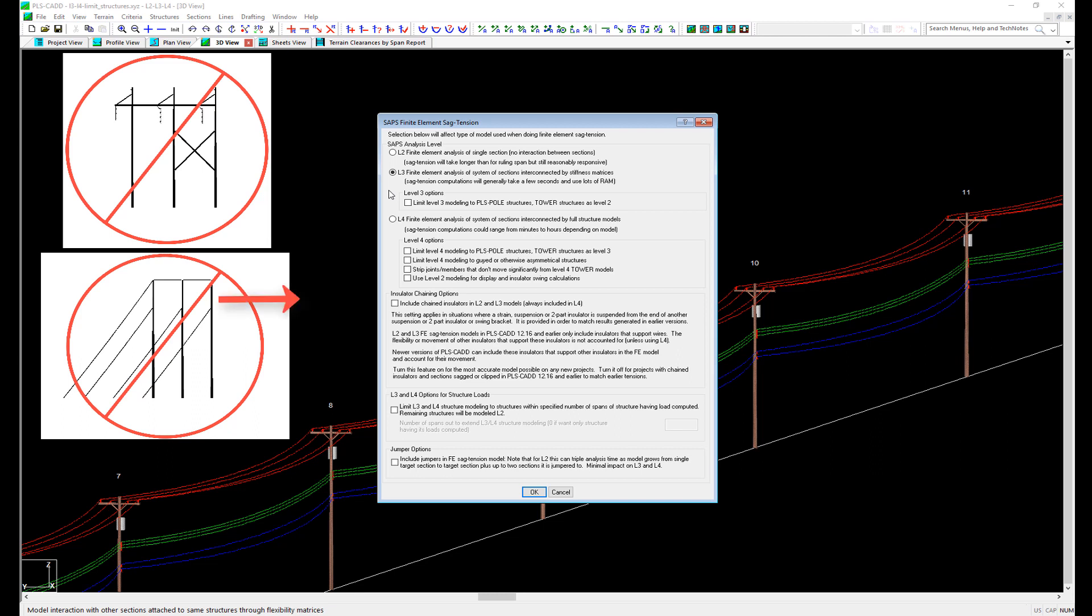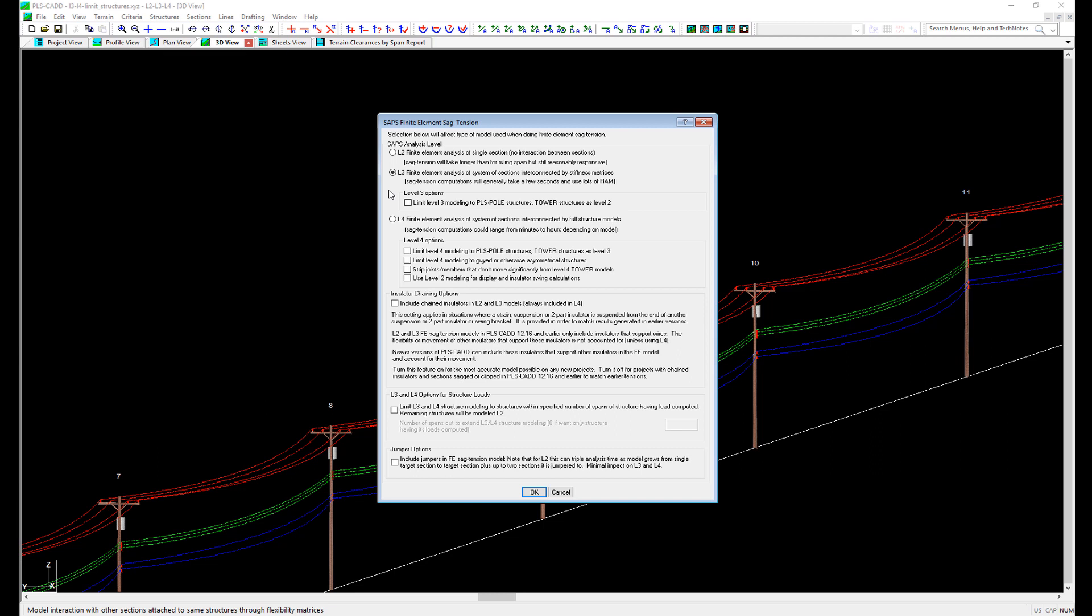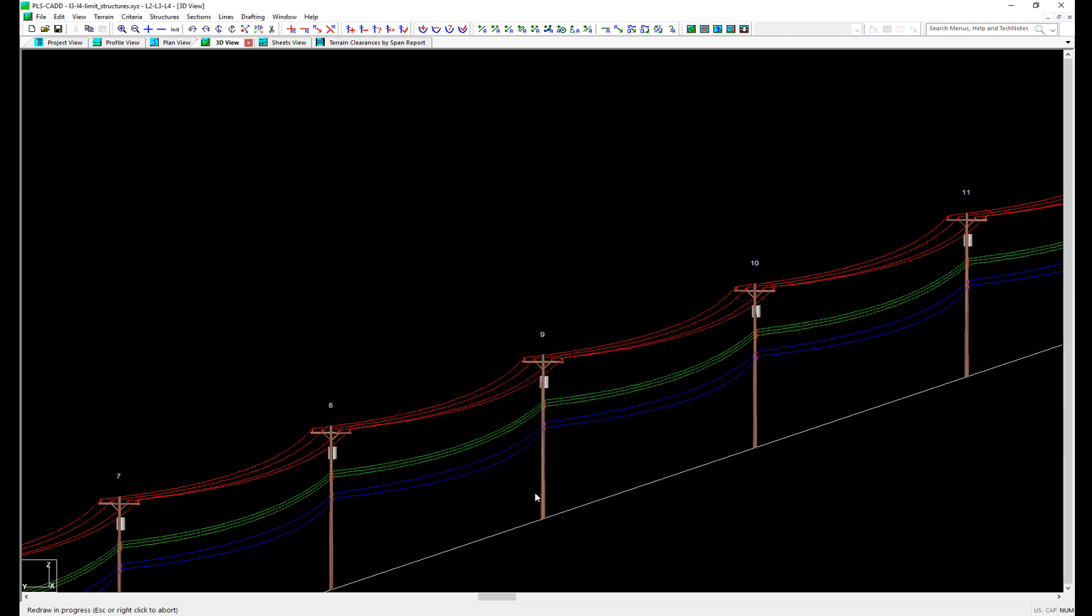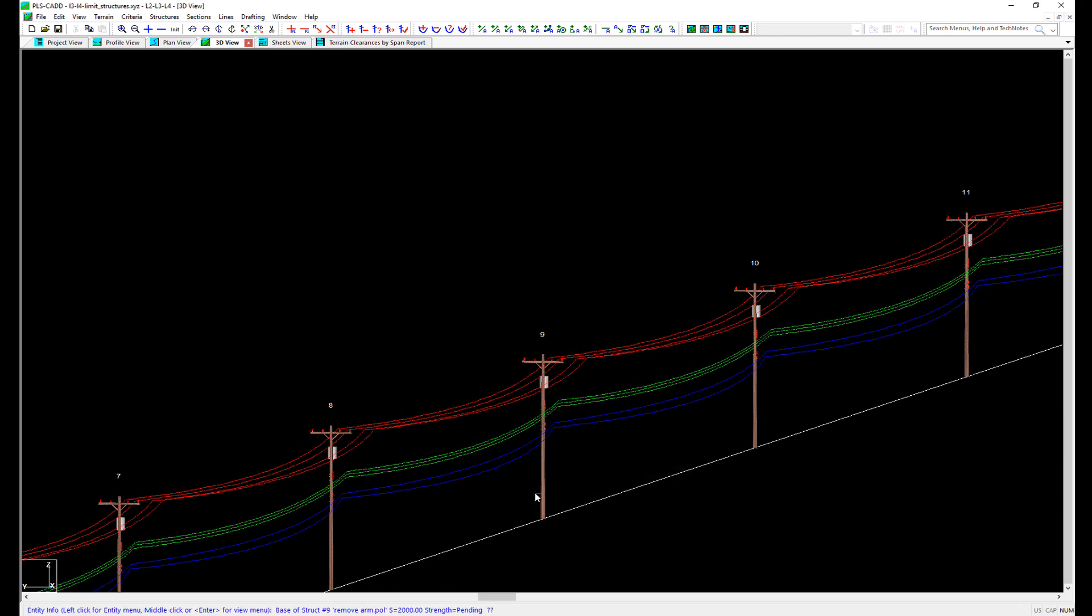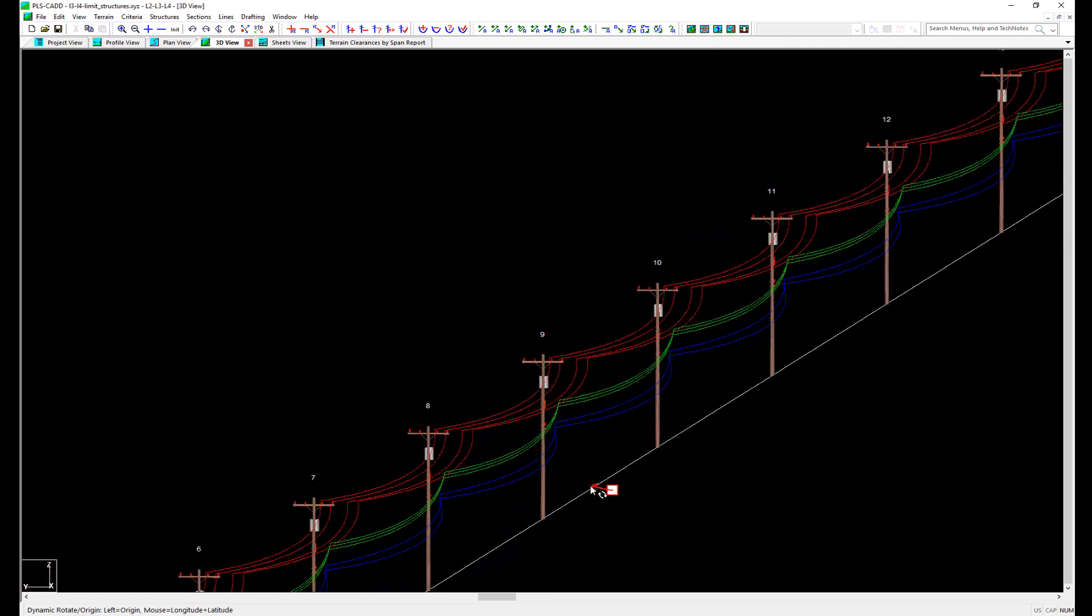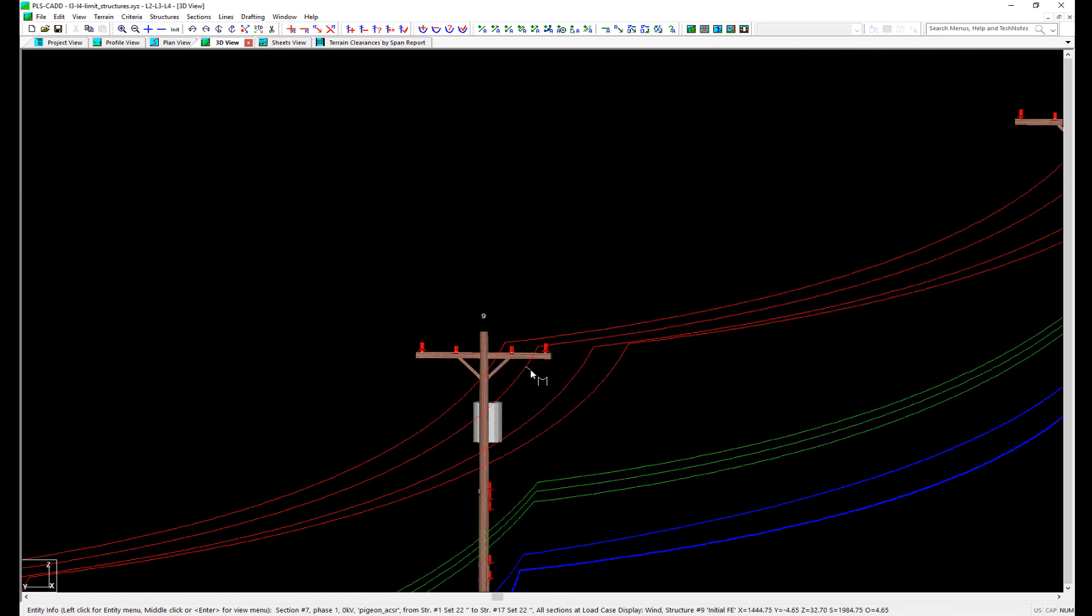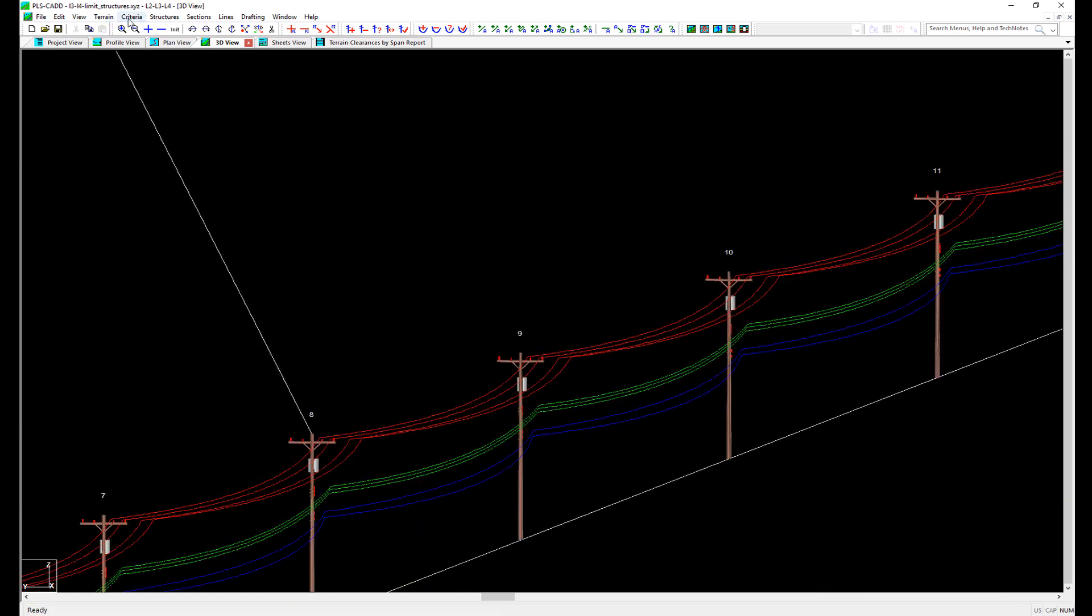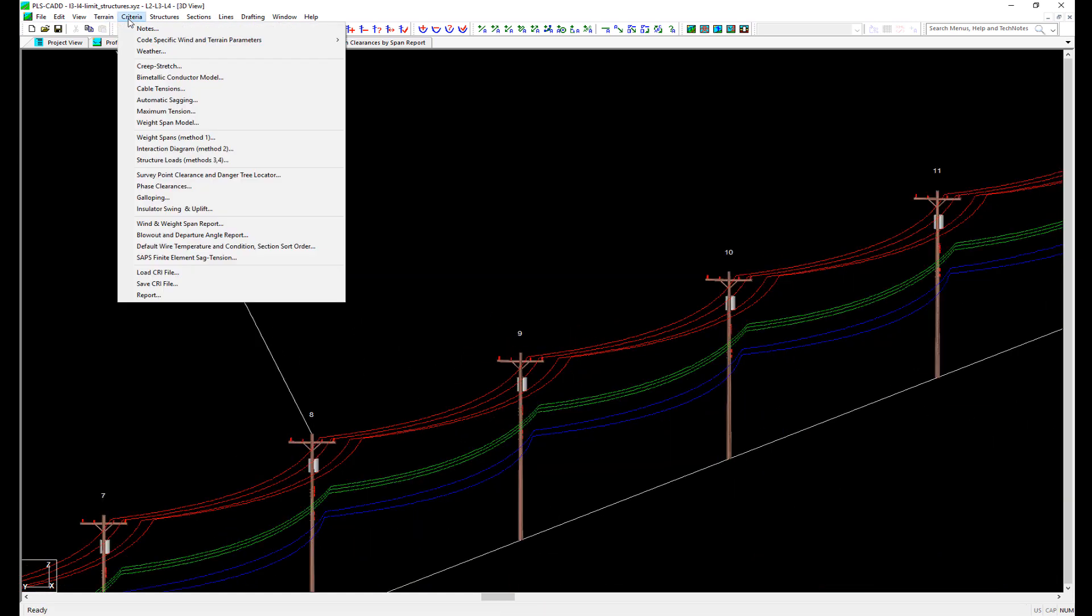For example, a guyed structure is stiffer when you have load pulling against the guys than load pushing into the guys. So any structure that has guy wires on it or has different stiffness in one direction versus the other should not be analyzed with SAP's level L3. There is also the option when using L3 analysis to limit it to just PLS-POLE structures and not tower structures. Towers are typically very rigid structures, so it may be acceptable to model these in SAP's level L2 and the other structures as SAP's level L3. Once we click OK, the display updates and the wires appear to be disconnected from the structures because PLS-CADD is showing the positions of the wires considering structure deflection for all structures in the model that are in the same section of conductor as Structure 9.